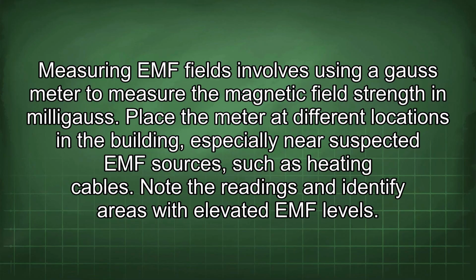Measuring EMF fields involves using a Gauss meter to measure the magnetic field strength in milligauss. Place the meter at different locations in the building, especially near suspected EMF sources, such as heating cables. Note the readings and identify areas with elevated EMF levels.